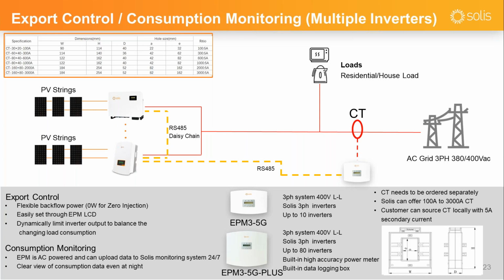For the Plus version, it actually has a built-in high accuracy power meter inside, because you see the Plus version is quite a bit bigger compared with the 5G version. So it has a high accuracy power meter inside, together with the data logging box. This means if you purchase the Plus version EPM, you will have the export power control solution, the consumption monitoring solution, and the general monitoring box inside the EPM box. So you don't need to buy an extra Wi-Fi box or any other data logging sticks for the monitoring. And for the three-phase EPM, we can also provide the CT, with specifications shown here. We can provide from 100 amp to 3000 amp, depending on your system needs.